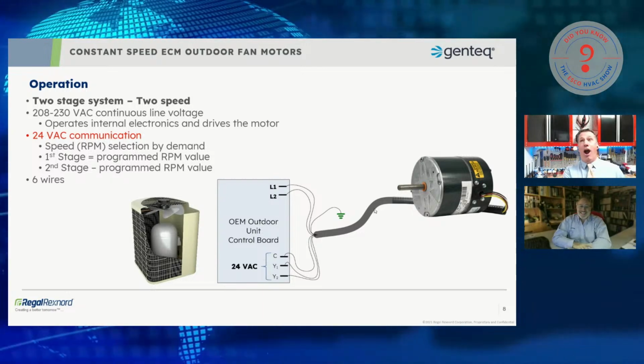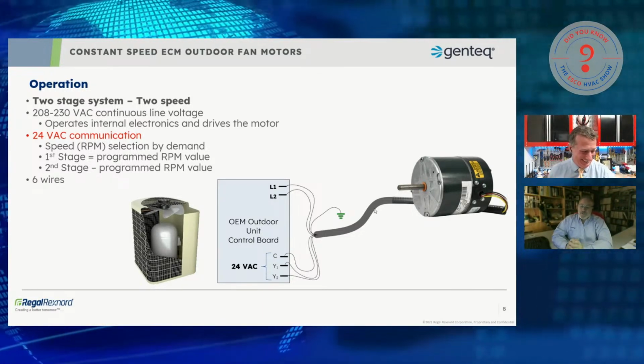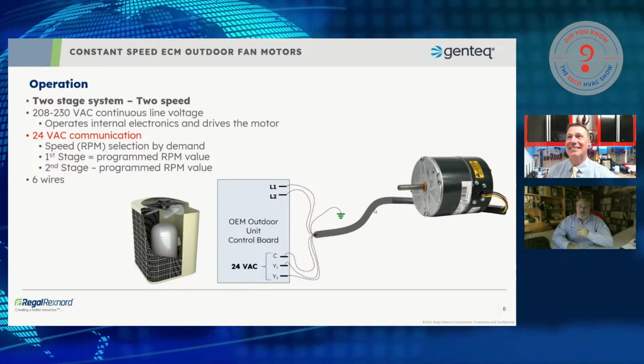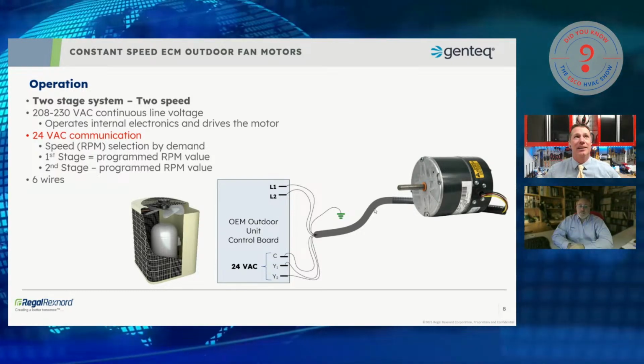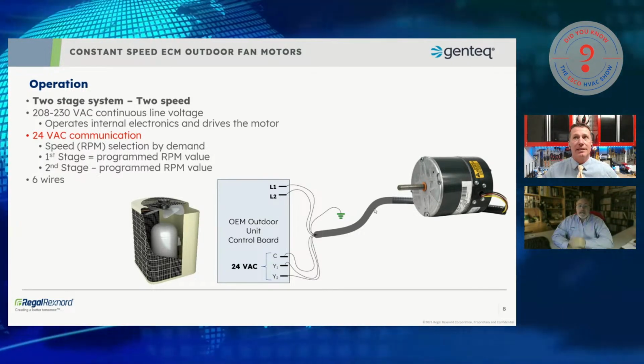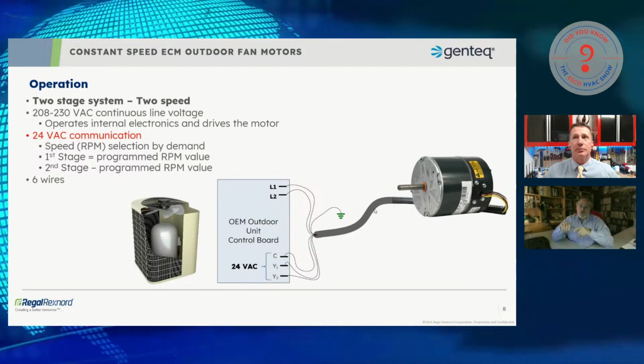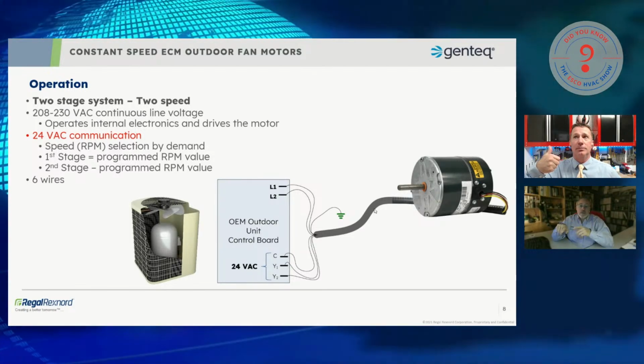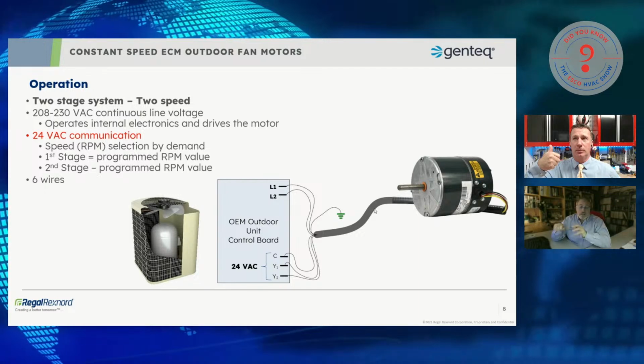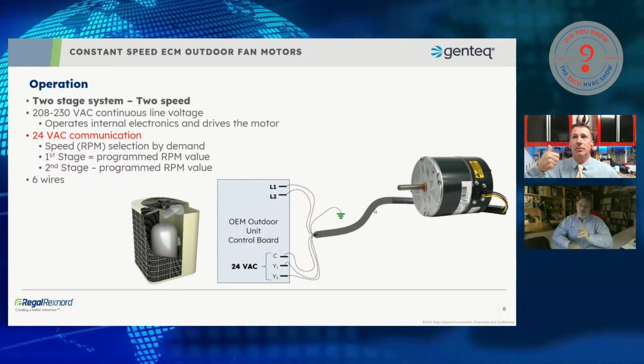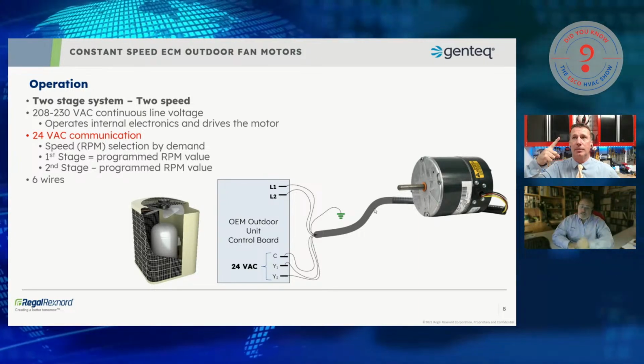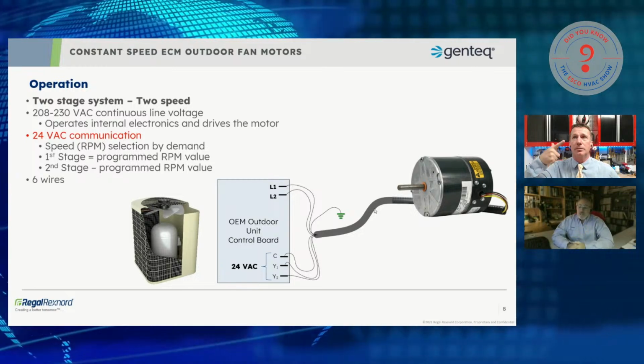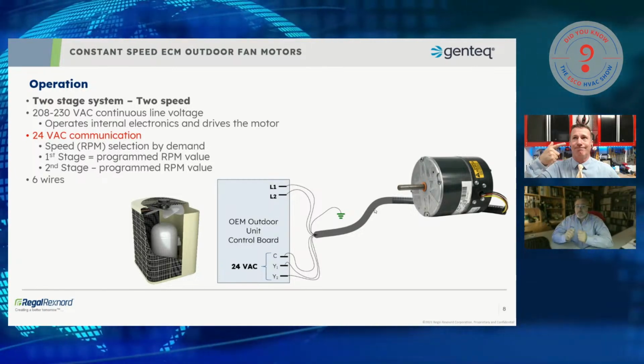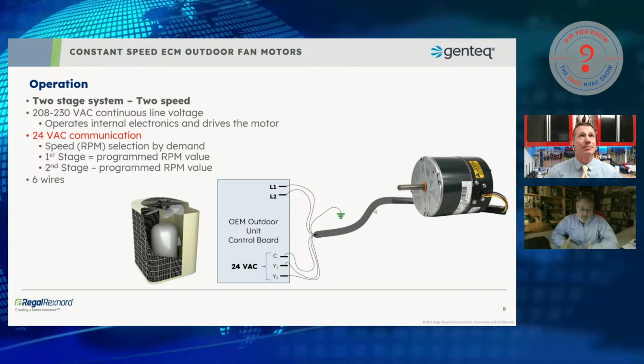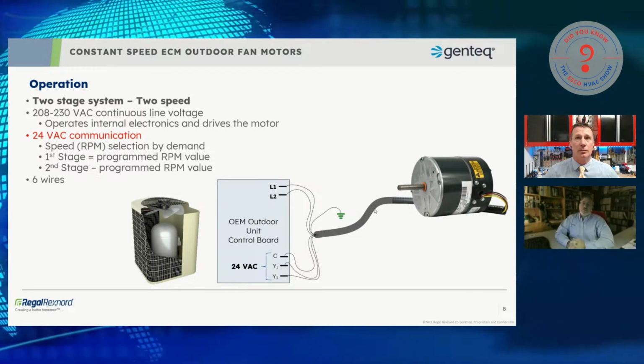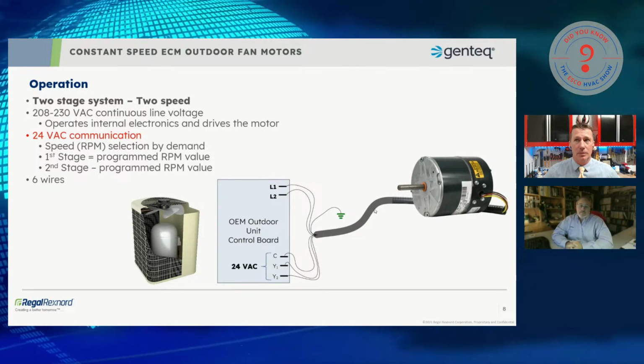So yes, absolutely. One option on the 2-wire 24-volt discrete speed motor is they can get a 3rd speed. Yeah, I can see that. To get the 3rd speed, you would get speed 1 by energizing wire 1, whatever wire color it's dictated as. You'd get speed 2 by de-energizing wire 1 and energizing wire 2. And then you'd get speed 3 by energizing both at the same time. Love it. And in a 2-stage unit, most often that 3rd speed is used for some kind of low ambient mode. Yeah, I got that.